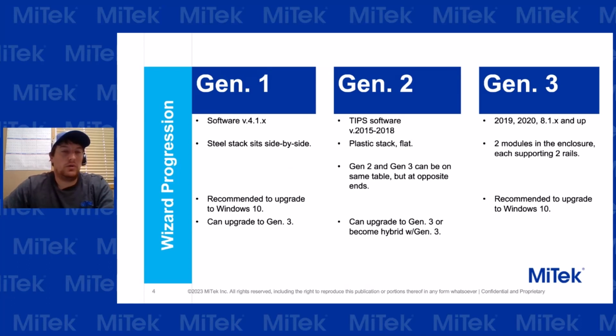Gen 1 right now we don't have the parts for it. We're upgrading that to Gen 3 as we go along. Gen 2, we've got TIPS software 2015 through 2018. I think there might even be 2014, 2013, but for the most part, if we see it, we upgrade it to 2018 because it has more features. The PLC stack inside of it is not side by side anymore. They are stacked on top of each other and facing vertical. Again, the orientation is the bottom big card is your PLC, the 2 middle cards are your high-speed counters, and the top card is your I/O card.